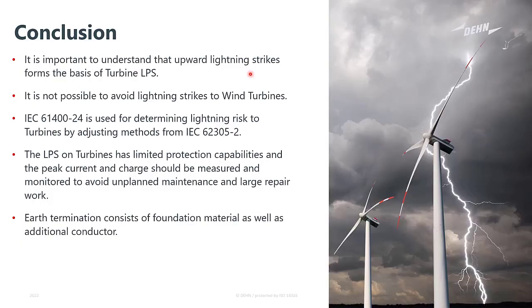It's also important to understand that it's not possible to avoid lightning strikes to wind turbines. IEC 61400 makes mention of lightning increasing within an area where a wind farm is being erected, and the standard also gives you methods for determining the lightning risk to a turbine and the number of events to a turbine. The lightning protection systems on turbines do, however, provide limited protection, and they have limited capabilities in terms of what they can handle through peak current and charge.